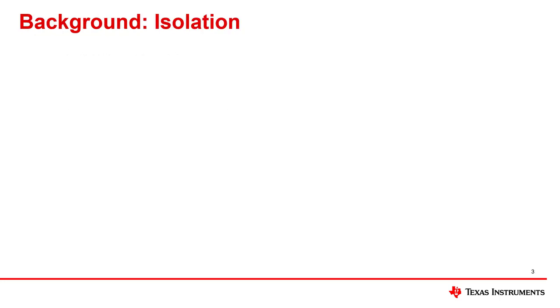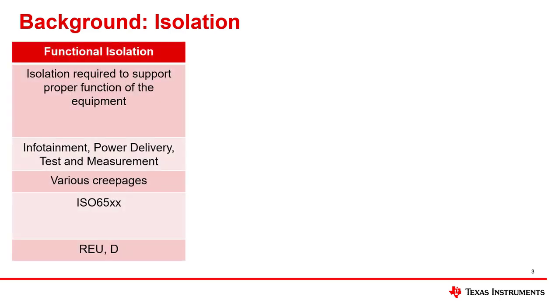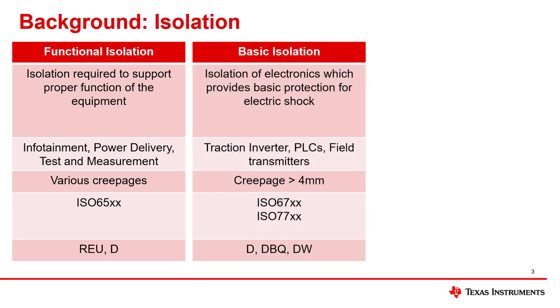Let's go over some background of isolation. There are three main types of isolation. We have functional isolation, which ensures the proper functionality of a system — we will be talking more about this in the next slides. We have basic isolation, which while maintaining system functionality also provides a layer of protection against electrical shock. This added safety feature, even in systems with rare human contact, ensures a safe working environment.